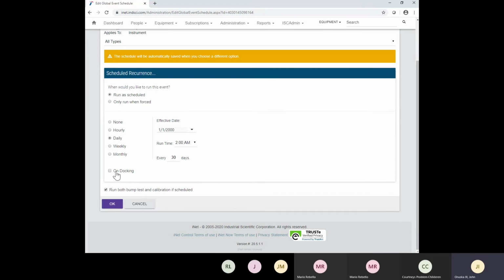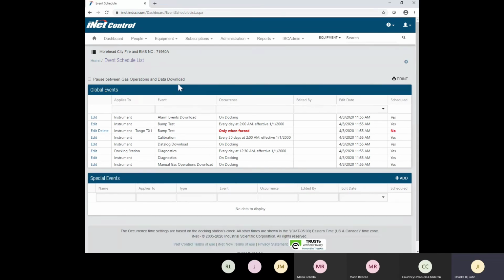And then also on docking. If you check that on docking, what will happen is every time you dock the instrument, it will do a bump test. That way nobody's got to worry about, has it been 12 hours since the last time it was bump tested? If I stick it in, is it actually going to go? All you have to do is just stick it into the docking station and it will run through and do the bump test. So, again, I'm going to click on cancel. And you guys can turn that on whenever you want.